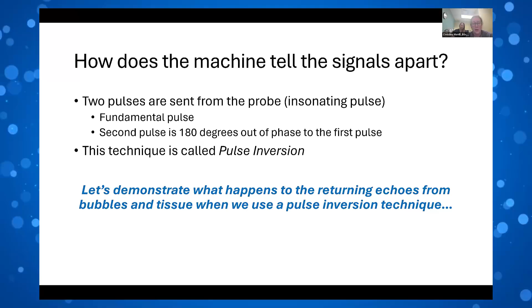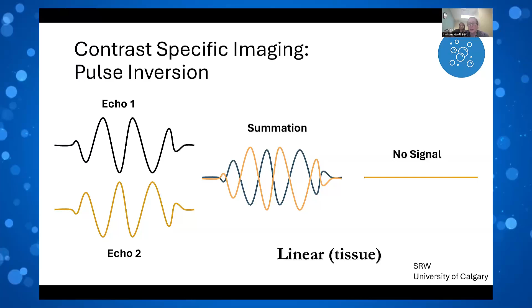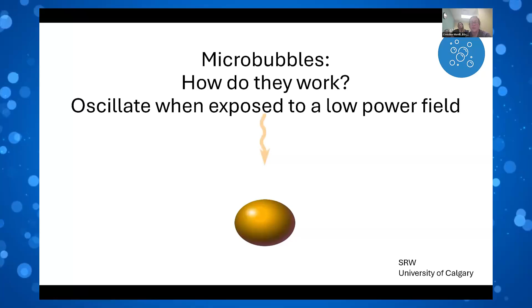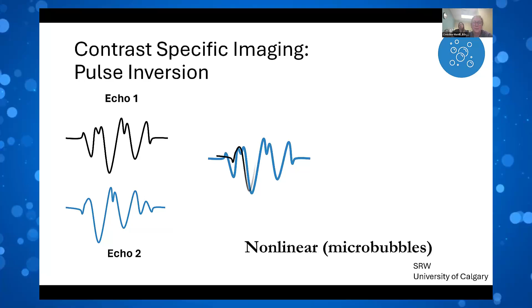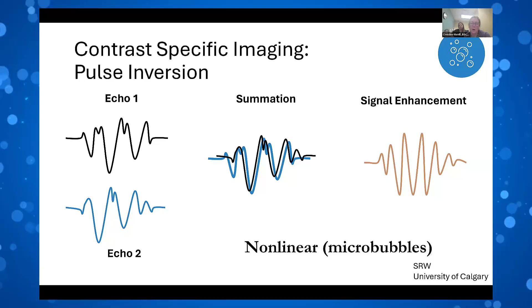This is an example of the returning echoes from tissue. You can see the echo 1 waveform, and you can see the echo 2 waveform, which is 180 degrees out of phase from echo 1. And when you sum these two, the summation of these two waves gives you a net zero signal. So when you subtract them, you get no signal. This is really important, and we're going to look at this concept a bit. So how do microbubbles work? They oscillate when they're exposed to a low power field. And the returning echo from bubbles, you get two waves here, you see echo 1 and echo 2. The two waves resemble each other. And the summation of the bubble waves creates signal enhancement. This is part of the nonlinear properties of bubbles.